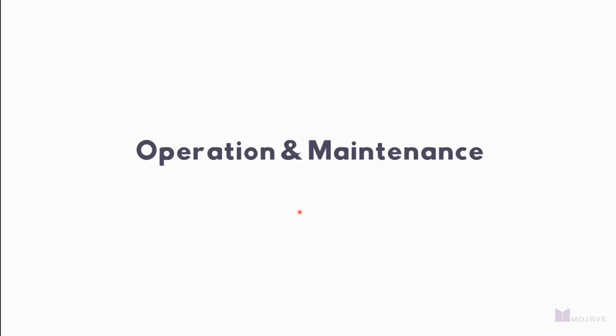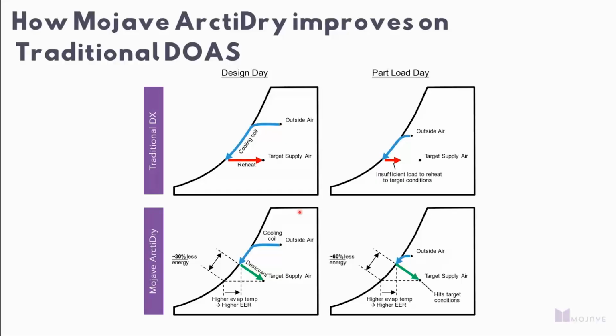So looking at operation and maintenance, from an operational standpoint, as we unload and do part load operation, we get even more efficient than a traditional refrigeration driven, or like an inverter or variable speed refrigeration driven system. And the reason for that is we're still cutting off that lower corner of the energy that you would need to tackle with a hot gas reheat or vapor compression system in a low ambient day. So letting the liquid desiccant do the bulk of the effect, again, effect because it's not work, to dehumidify in a lower ambient day.